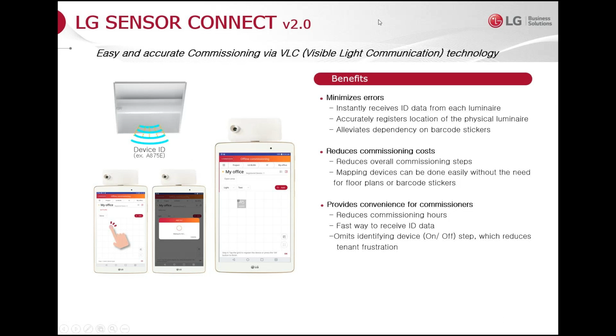This minimizes a lot of errors. Installers might put the barcodes in the wrong place, floor plans might get destroyed, or the commissioning agent might input the data wrong by making a typo. With this, we reduce that. It's a one-for-one correlation: you're under the light you know you want, and the device isn't relying on the user to input the data, it gets it automatically. This improves on having to go back to areas that were commissioned incorrectly or put in the wrong place, and it's the fastest way to get through every room and register every light for more accurate commissioning. Overall, we're helping installers have an easier time installing our lights, and reducing commissioning hours spent troubleshooting on site versus just getting in and out of every room.